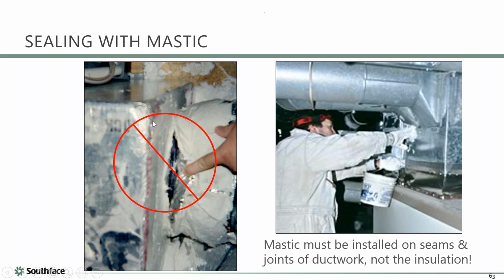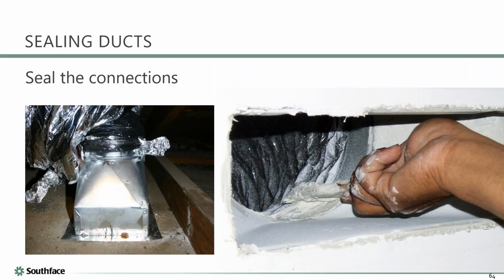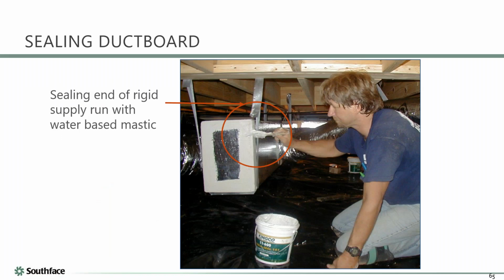Again, if we see mastic on the outside of the flex duct, we start to get suspicious, because that means someone's either trying to fool the code official or doesn't know what they're doing. It's the inside pressure liner that matters, and the inside seams of metal duct. You can retrofit seal ducts from the inside if you have a boot and flex duct connected to it. Reach inside. I usually use a glove and just goop mastic from the inside and seal all the seams. This is the main connection we're really trying to get, as well as all these little seams. And of course, seal the boot to the drywall.